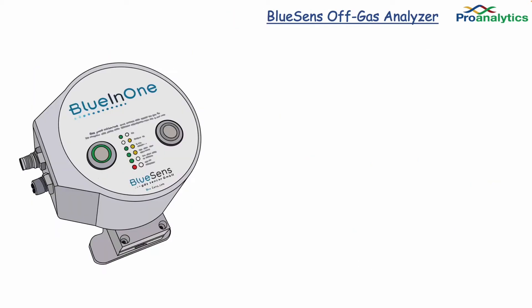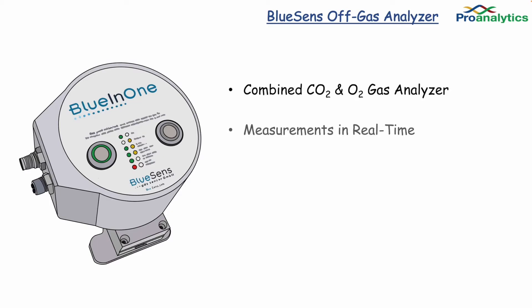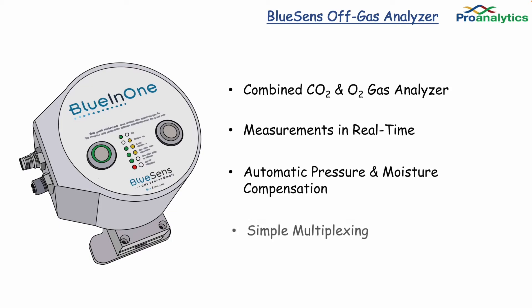BlueSens is a non-invasive real-time gas analyzer that attaches to the exhaust of your reactor. Here is the BlueInOne sensor, which measures CO2 and O2 off-gas in real-time. The sensor automatically compensates for pressure and humidity during the run.